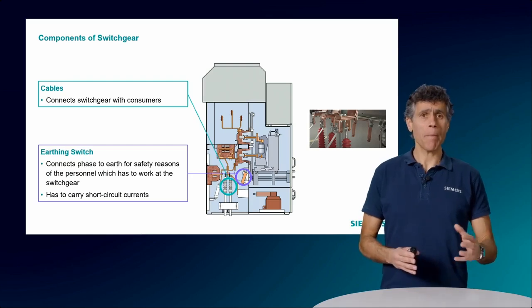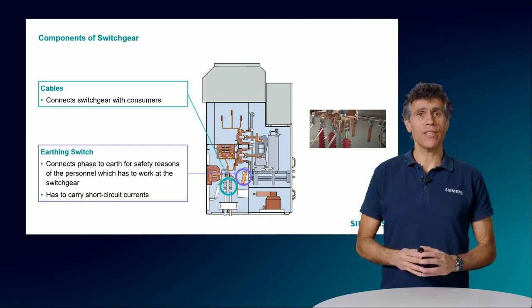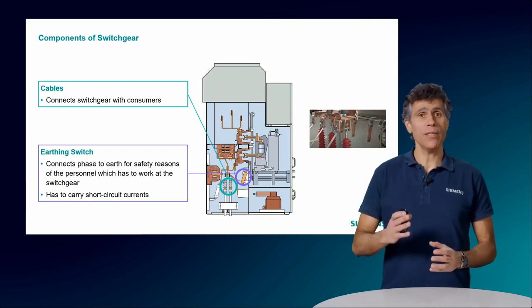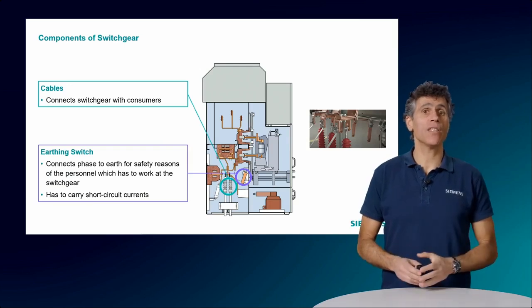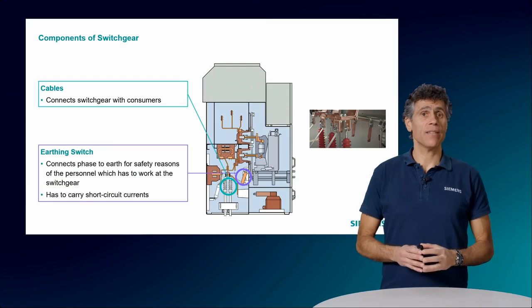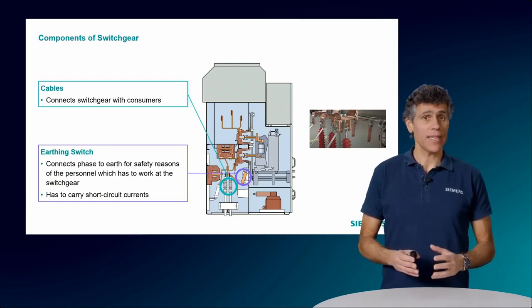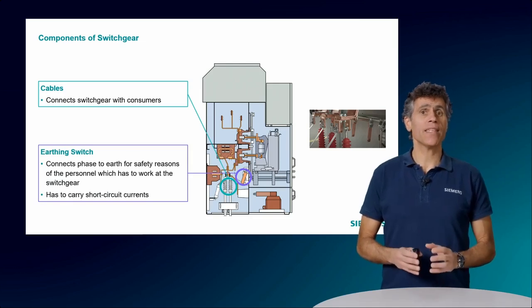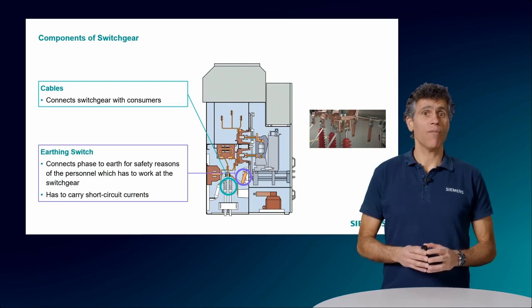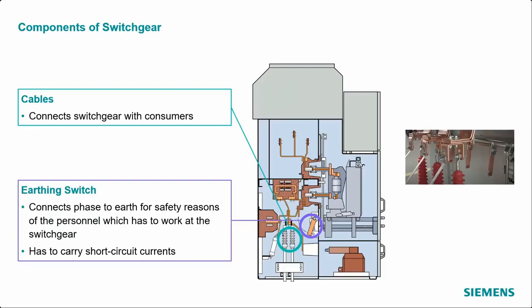This is why often a padlocking facility is required. When the operator needs to touch the cables, he puts the earthing switch on and he keeps the key in his pocket so that no one can turn it off again. While the earthing switch is connected, nothing can happen to the operator. As you might have guessed, the earthing switch is usually capable of withstanding a short circuit. If an operator is working and the voltage is turned on, the earthing switch will withstand that huge power flow until the upper protection mechanism shuts off the failure, typically within 1 or 3 seconds. The other way around, if the earthing switch is switched on while there is still voltage, a failure occurs and the earthing switch must hold its earthed position until the fault is cleared. This way, the operator is always safe.